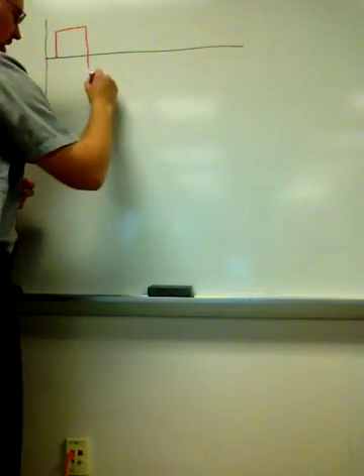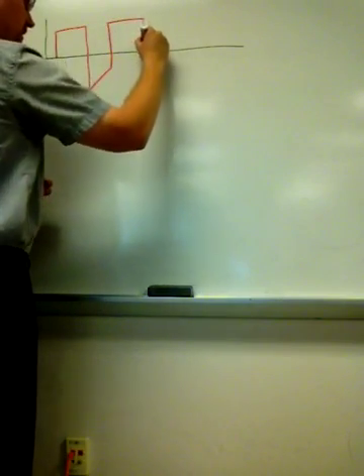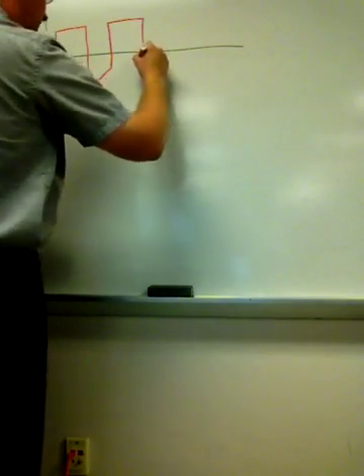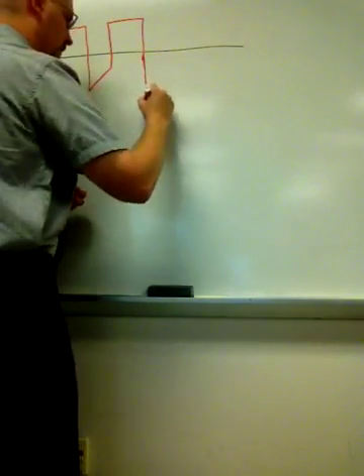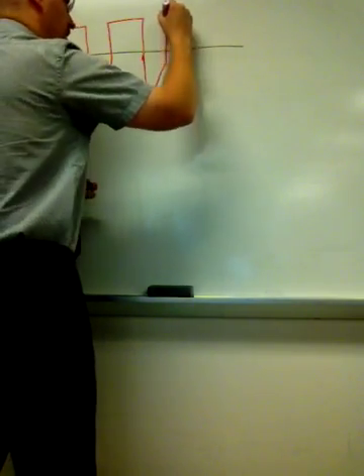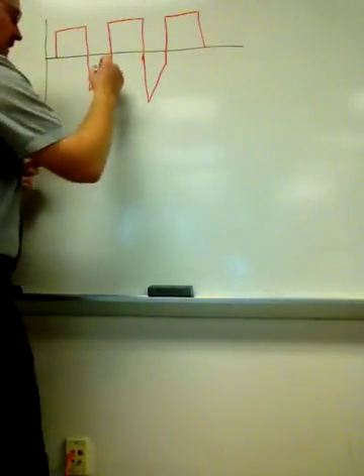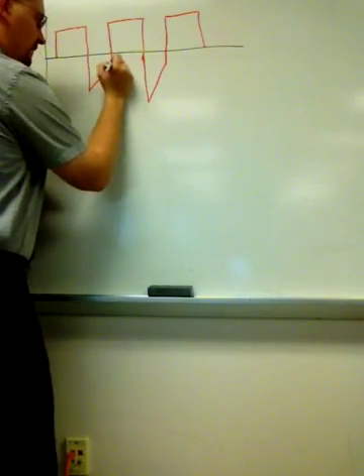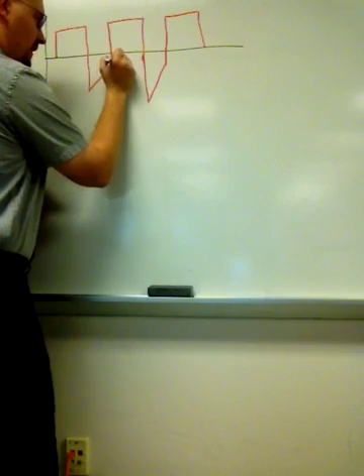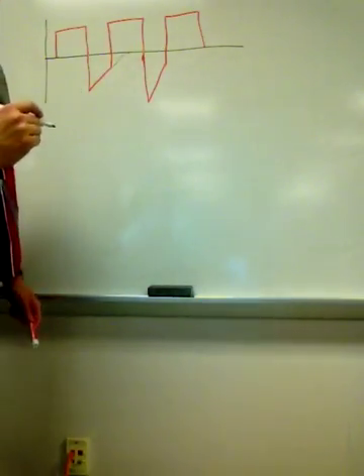And it is going to look something like this, where I am going to be in my expiratory phase, and then my next breath will be delivered in the expiratory phase itself. So let's just go ahead and draw another one here, just like this. Now you can see that this line here should have, we should have allowed that line to return to zero, return to the baseline.